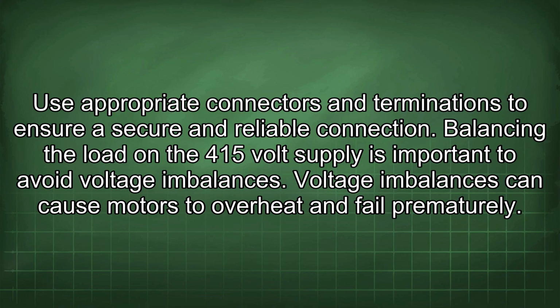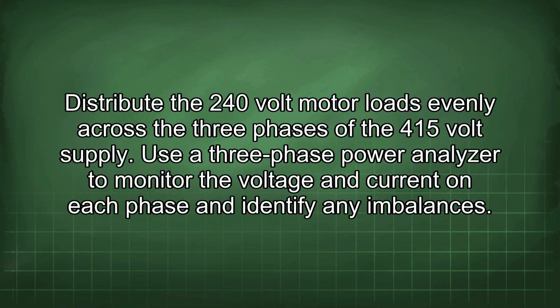Balancing the load on the 415-volt supply is important to avoid voltage imbalances. Voltage imbalances can cause motors to overheat and fail prematurely. Distribute the 240-volt motor loads evenly across the three phases of the 415-volt supply. Use a three-phase power analyzer to monitor the voltage and current on each phase and identify any imbalances.